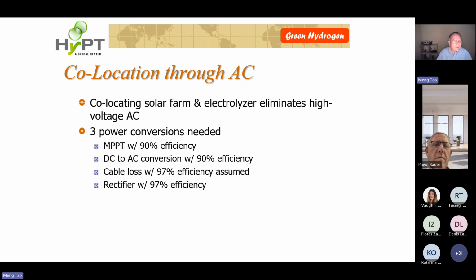Let's see. Okay, here. If we do co-location through AC, then we don't need high voltage, so we can get away with 500 volts, 600 volts, but we still need to do maximum power point tracking. That's 90% efficiency. We still need to do DC-AC conversion, 90% efficiency, cable loss, 97% efficiency, rectifier, 97% efficiency.